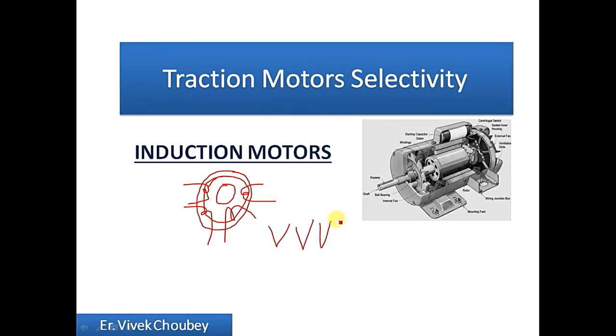We use VVVFD, that is variable voltage variable frequency drives. What they do: these VVVFD drives actually make the ratio of V to F such that the flux remains constant, the magnetic field flux within the motor remains constant.